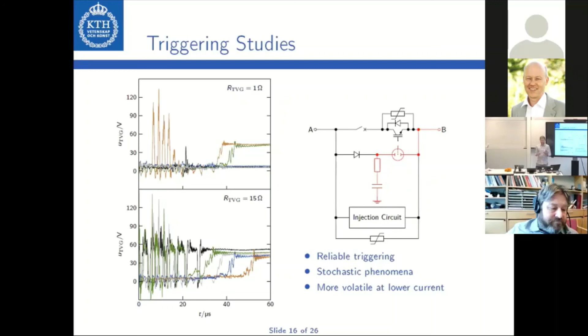In this configuration, the converter is placed in series with the triggered vacuum gap, and this is a disadvantage in the aspect that it always conducts when the triggered vacuum gap conducts, which is somewhat longer than in configuration A. This converter then has to conduct a relatively high current for a relatively long time. But on the other hand, the IGBTs in Hitachi ABB's hybrid DCCB also have to conduct for the same kind of time, so I assume it should be feasible.